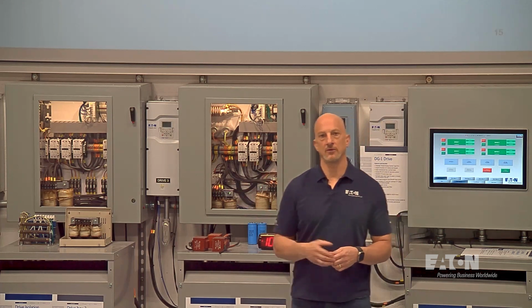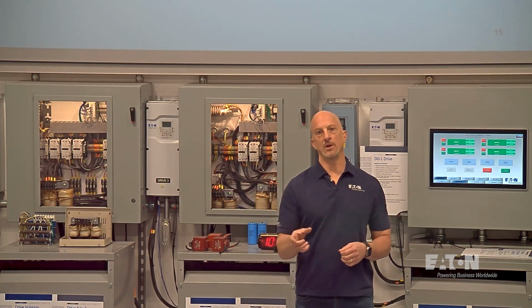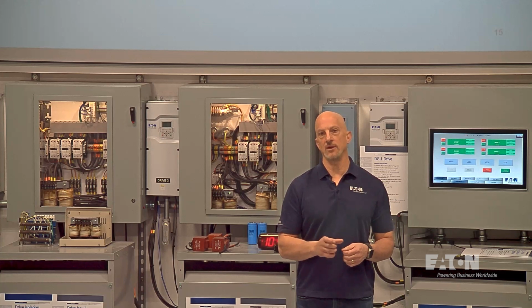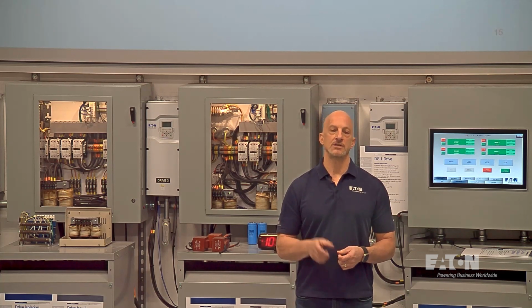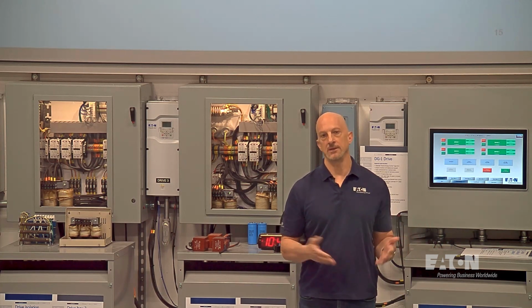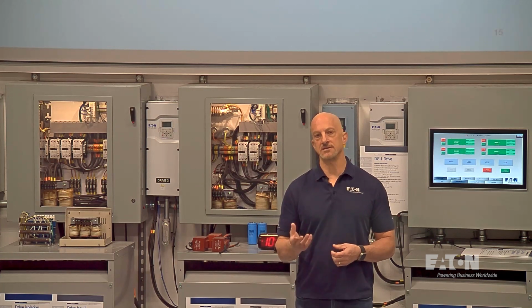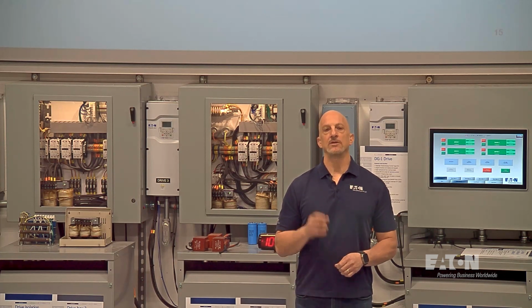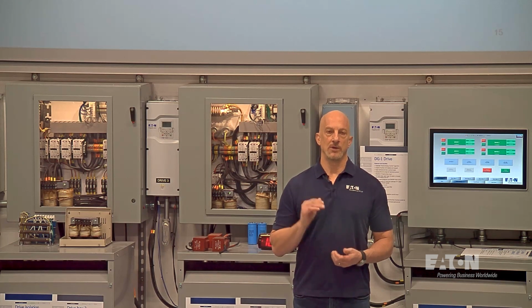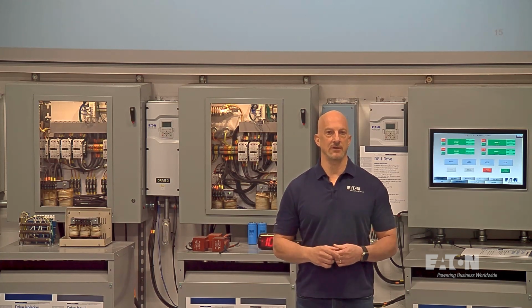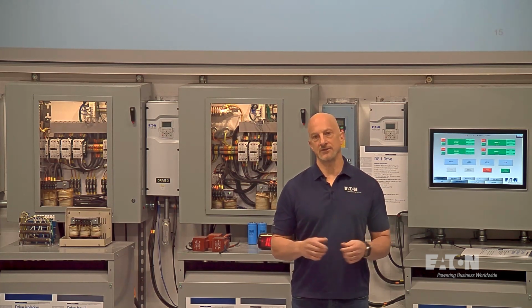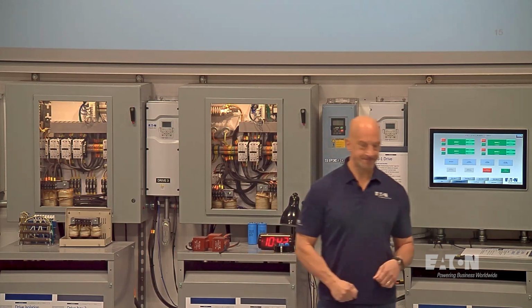drives up here. So if we take the drives, if you put one drive on, it draws about 12 amps of fifth harmonic current. So you would think all 4 drives would be roughly 48 amps, and it turns out to be about 42 amps. But there's a reason that the harmonics reduce, and it's not because they're canceling with each other. I'll show you an example of why that works on paper.